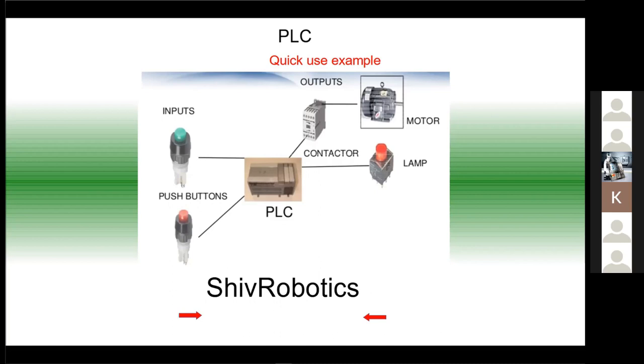The PLC cannot directly control single phase or three phase motors, that's where the contactor comes in. You can see the white box between the motor and PLC, this is the contactor, which is driven by the PLC and in turn drives the motor. We also have a lamp connected which can be used as an indicator.